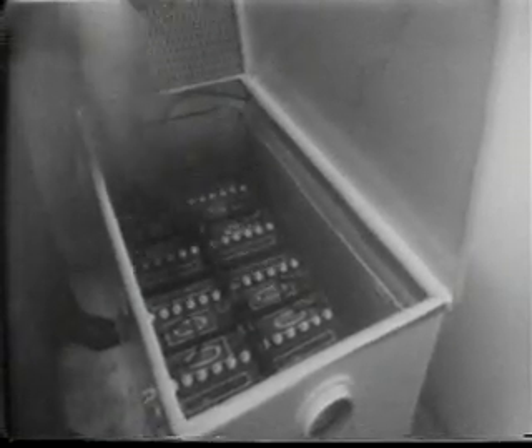While you're at the power pack, check the batteries to see that they are fully charged and that the cables are in good condition. Each cell should have a specific gravity of at least 1.265.